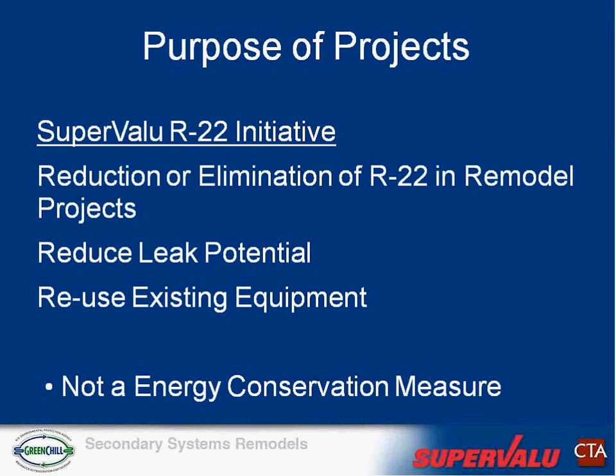We do have an R22 initiative at SuperValu. We're focused on looking at ways we can reduce or eliminate R22 in remodel projects, reduce leak potential in all of our R22 stores, and keep them as tight as possible. We've got some projects looking at the reuse of existing equipment. A lot of stores that come up for remodel haven't met the full life of their rack systems or compressor systems, so we're looking for ways to reuse that equipment in a non-DX mode, turning it into a system where we can save refrigerant charge and reduce leaks.